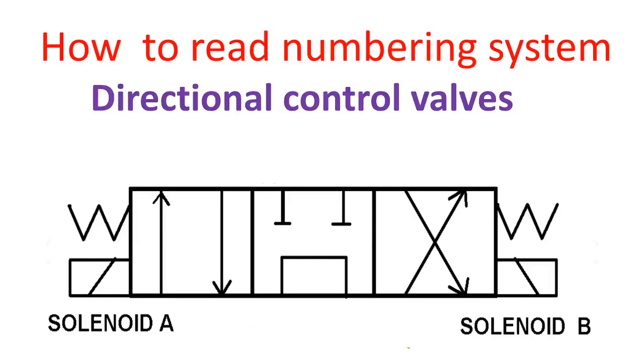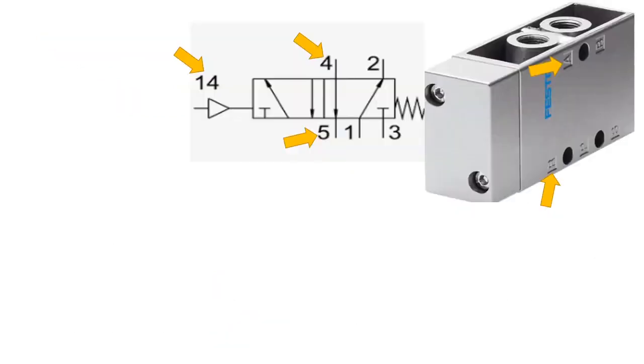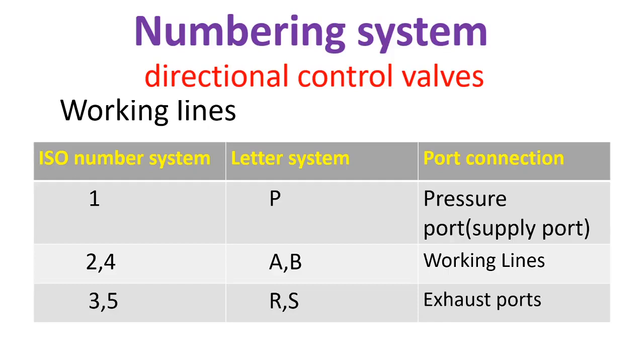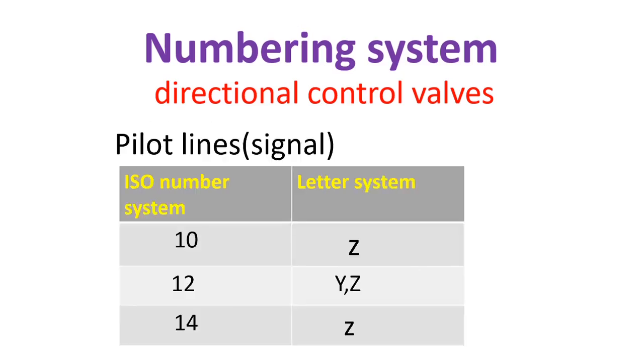Our next topic is the numbering system of directional control valves. If your valve uses numbers or letters for port designation: number 1 or letter P is the pressure or supply port. Numbers 2 and 4, or letters A and B, are working lines. Numbers 3 and 5, or letters R and S, are exhaust ports. For pilot lines or signal: 10 equals Z, 12 equals Y or Z, and 14 equals Z.